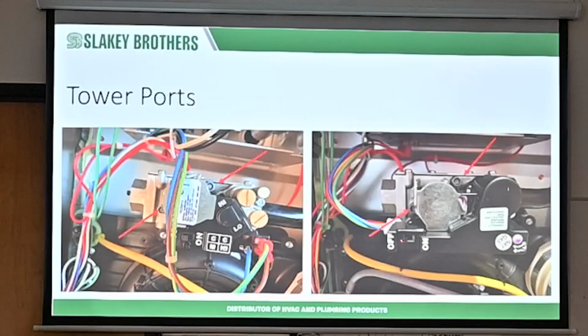Your modulating gas valve, it modulates. You can see it's a whole different connection there. Internally, it's going to be communicating with the circuit board, and it's going to know how much to open and how much to close. But you've got to calibrate it. You've got to calibrate it. You've got to make sure that it's done precisely.